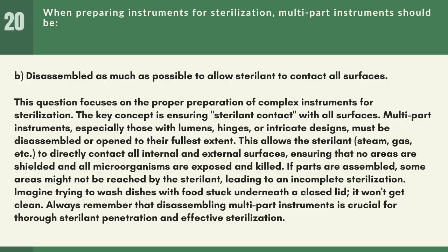If parts are assembled, some areas might not be reached by the sterilant, leading to an incomplete sterilization. Imagine trying to wash dishes with food stuck underneath a closed lid; it won't get clean. Always remember that disassembling multi-part instruments is crucial for thorough sterilant penetration and effective sterilization.